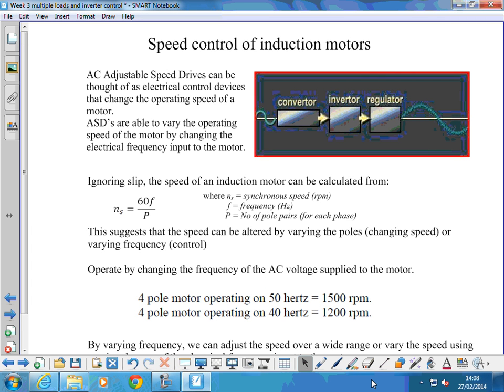So, adjustable speed drives can be thought of as an electrical control device that changes the operating speed of the motor. They are able to vary the operating speed by changing the electrical frequency of the input to the motor. In its most basic form, there is an AC input with some kind of converter, an inverter, and then regulating the output to have a variable frequency supply. We'll look at that in a little more detail later.